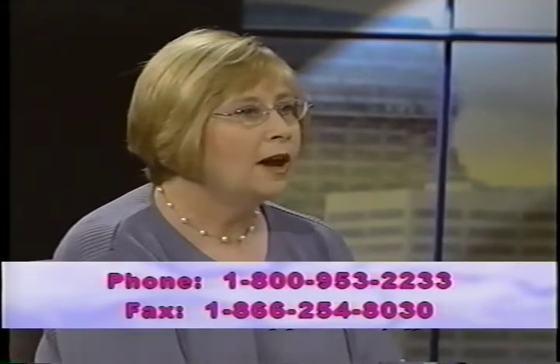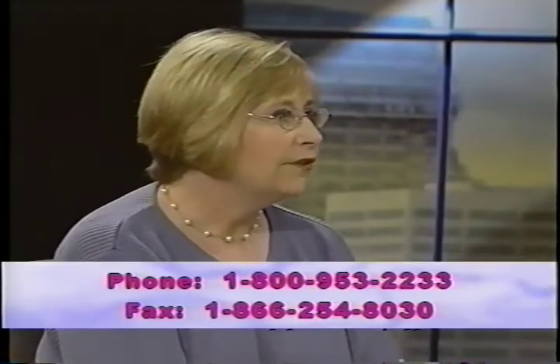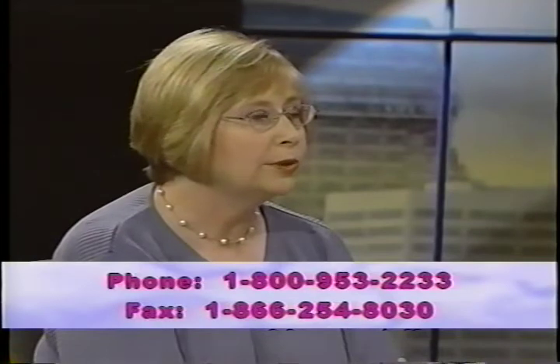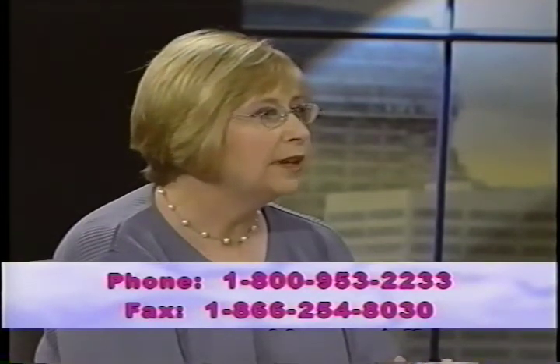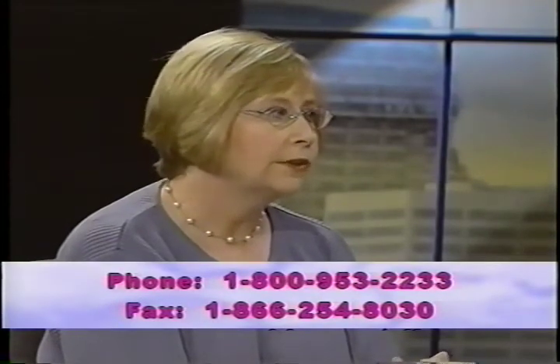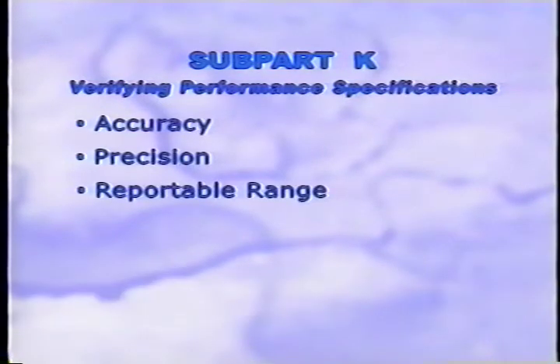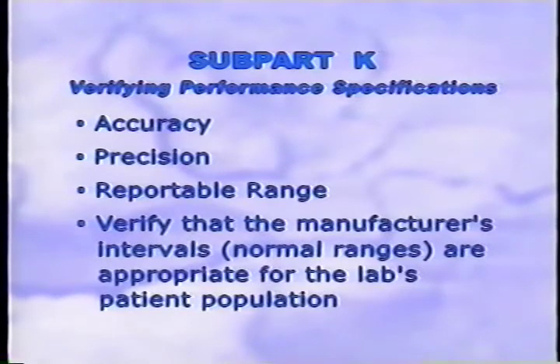Do laboratories have to verify the performance specifications for all the tests currently being performed? Labs performing unmodified moderate complexity testing are not required to verify performance specifications for any test system used prior to April 24, 2003. Well, Diana, what do labs have to do now for performance specifications? Well, the final regulations require that new, unmodified, FDA-cleared or approved test systems must have the following performance specifications verified by the laboratory, in the lab's environment, also using the lab's testing personnel, prior to reporting any patient results. And these are accuracy, precision, reportable range, and they must verify that the manufacturer's reference intervals, or normal ranges, are appropriate for the lab's patient population.